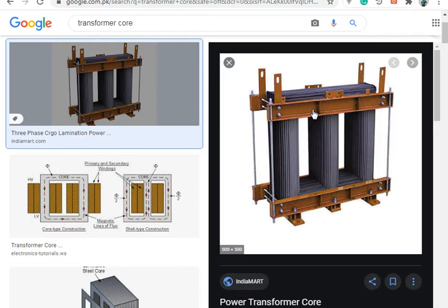Search that word. That movement of the core laminations has to be confined, because otherwise it is constantly vibrating. What will happen? The windings will loosen, and when the windings loosen, you will have air flux, which is leakage flux. So a transformer has to be intact over there, certainly the core, and the windings also.